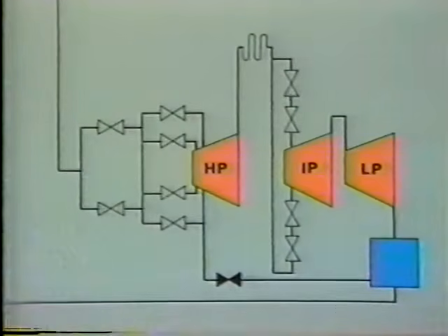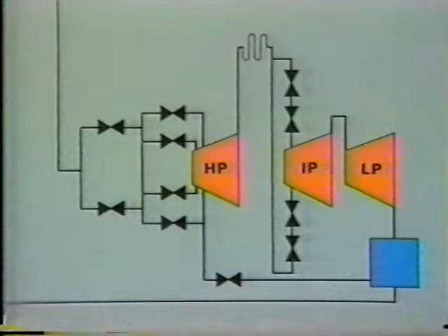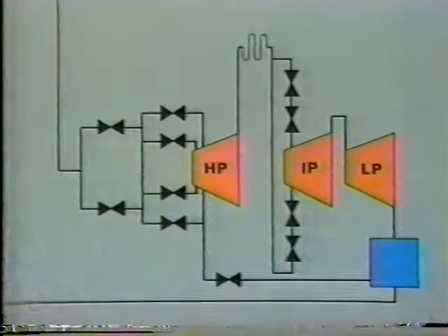or shut down. If the turbine trips, the valves that control the flow of steam through the turbine close. When these valves close, steam is bottled up in the high-pressure turbine. However, during this condition, the high-pressure turbine blades are still rotating. Since the steam in the HP turbine has no place to go, the rotation of the blades through the trapped high-pressure steam could generate a tremendous heat buildup and possibly damage the turbine's internal parts. Now let's see how the ventilator valve prevents this.